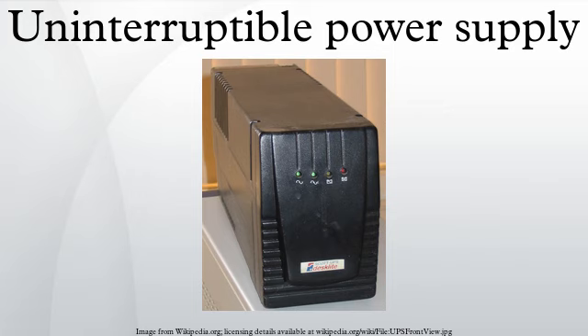It is also able to tolerate short-circuit conditions up to 17 times larger than an electronic UPS, permitting one device to blow a fuse and fail while other devices still continue to be powered from the rotary UPS. Its life cycle is usually far greater than a purely electronic UPS, up to 30 years or more. But they do require periodic downtime for mechanical maintenance, such as ball bearing replacement. In larger systems, redundancy of the system ensures the availability of processes during this maintenance. Battery-based designs do not require downtime if the batteries can be hot swapped, which is usually the case for larger units. Newer rotary units use technologies such as magnetic bearings and air-evacuated enclosures to increase standby efficiency and reduce maintenance to very low levels.